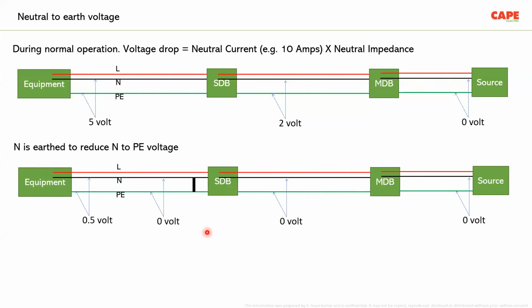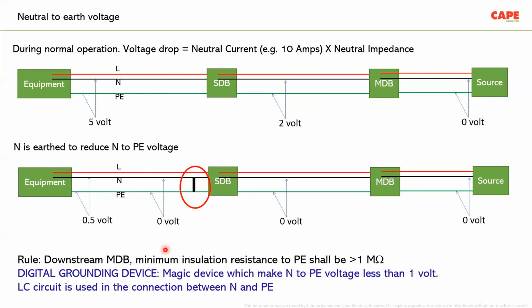Now, in the industry, people used to demand that more than 1 volt is a problem for their electronics, and they are not ready to work with more than 1 volt between neutral and earth. As a result, what the electrical engineers do is make a loop between neutral and earth. So here, where I'm moving the cursor, the neutral and earth are connected. This is actually a violation of the electrical safety rule.